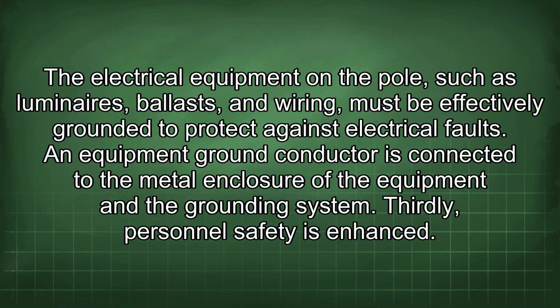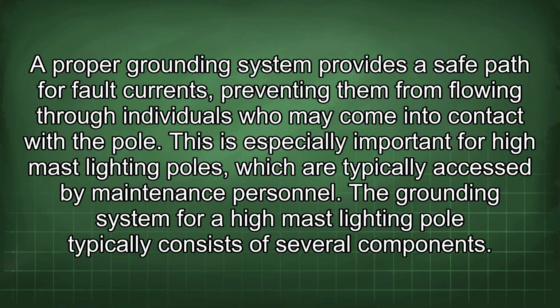The electrical equipment in the pole, such as luminaires, ballasts, and wiring, must be effectively grounded to protect against electrical faults. An equipment ground conductor is connected to the metal enclosure of the equipment and the grounding system. Thirdly, personnel safety is enhanced. A proper grounding system provides a safe path for fault currents, preventing them from flowing through individuals who may come into contact with the pole. This is especially important for high-mast lighting poles, which are typically accessed by maintenance personnel.